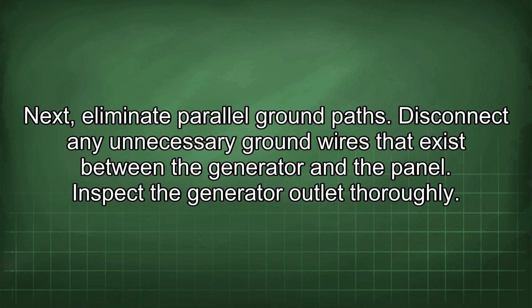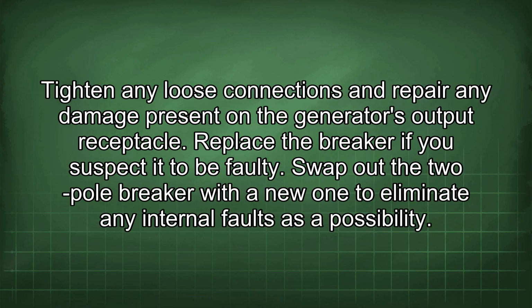Next, eliminate parallel ground paths. Disconnect any unnecessary ground wires that exist between the generator and the panel. Inspect the generator outlet thoroughly. Tighten any loose connections and repair any damage present on the generator's output receptacle. Replace the breaker if you suspect it to be faulty. Swap out the two-pole breaker with a new one to eliminate any internal faults as a possibility.